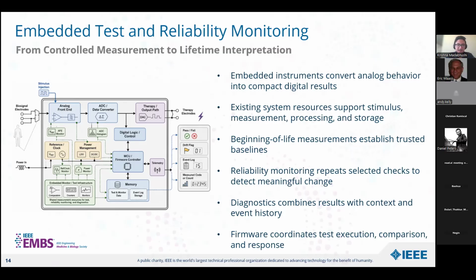That creates a kind of progression. The embedded test creates a controlled measurement. Reliability monitoring repeats selected measurements over time, looks for meaningful change, and then the diagnostics adds operating context and event history so that the change can be interpreted later. So the same internal infrastructure can support a few functions.